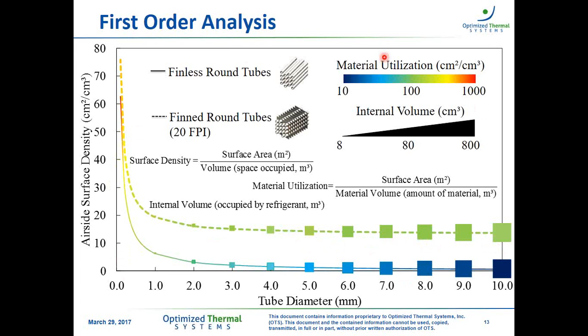But again, we also have a significant reduction in material required for the same surface area as we reduce the tube diameter. And lastly, indicated by the size of these symbols, is the internal volume. So if we go from 10 millimeters all the way down to 3 millimeters, we have a significant reduction in refrigerant charge. But why am I showing this?